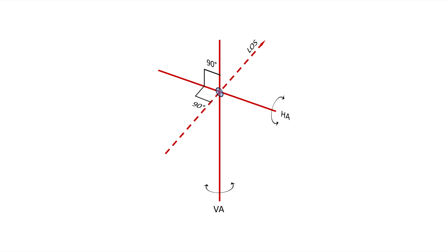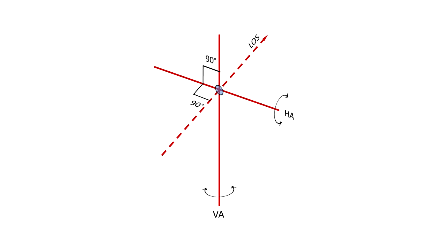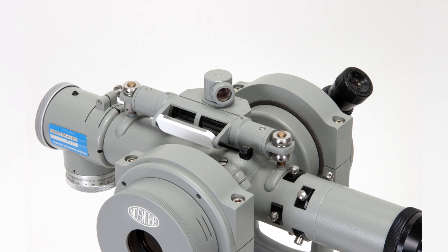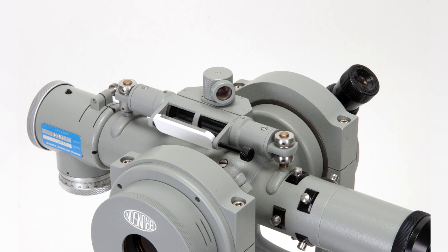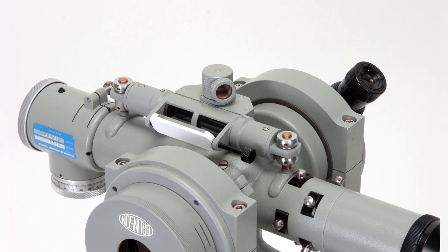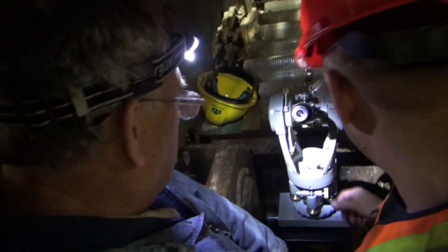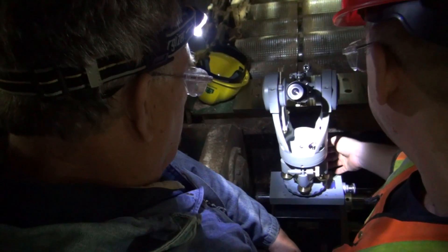The jig transit can also be precisely leveled, which allows a technician to create a gravity-based reference system from which all machine surfaces can be measured.